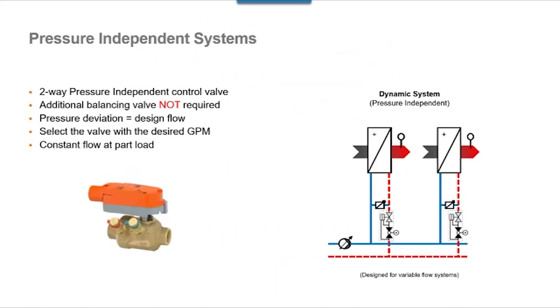A pressure independent control valve, as you see here on the slide, you notice the balancing device has gone away. Instead, your pressure independent valve is serving as both control and serving a purpose of the balancing valve. It's not the balancing valve per se, but you don't need a balancing valve with this. And Bob, if I could jump in here, sure.